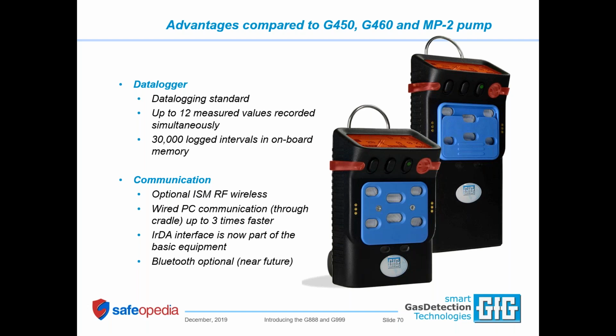We also have, of course, the communication options. It's not only the optional RF communication, but if you connect the instrument up through the charger cradle to a computer and you want to download the data, the speed at which the data is downloaded is 3 times faster than with the 450 and the 460. That's a good thing considering how much more data we have stored. We also include an IRDA interface, so we are able to communicate optically with the instruments, and in the near future we expect to be adding a Bluetooth communication option also.